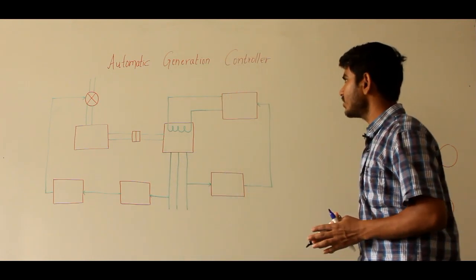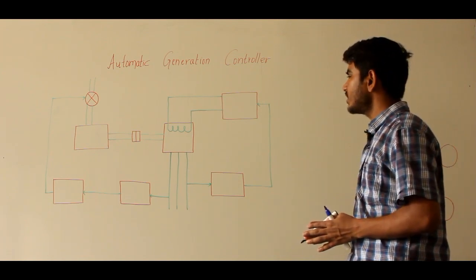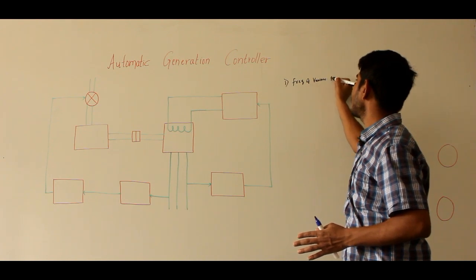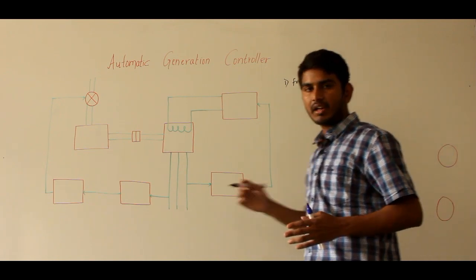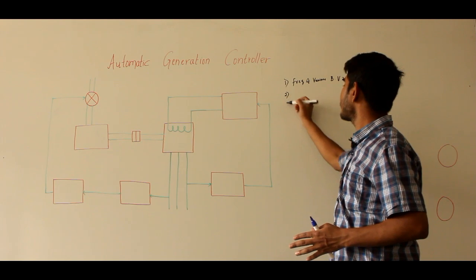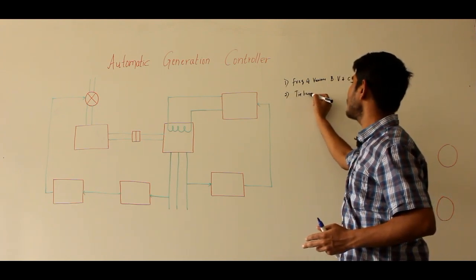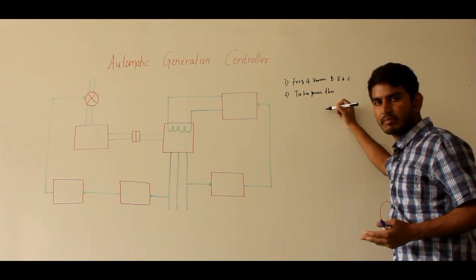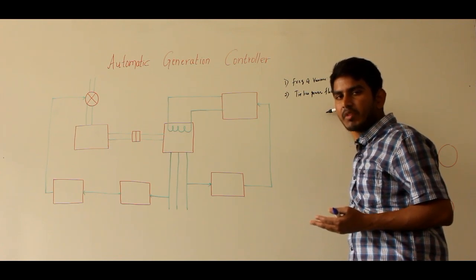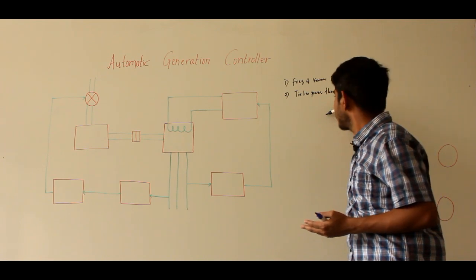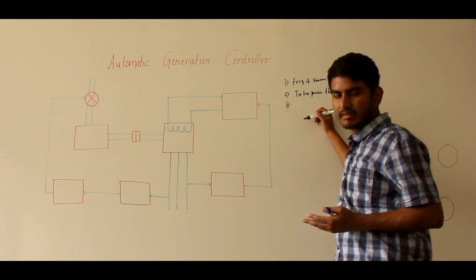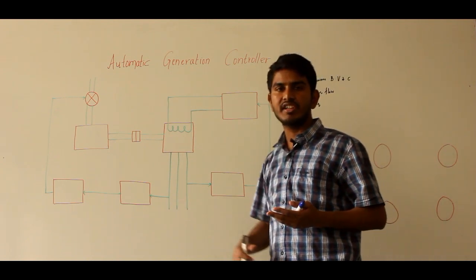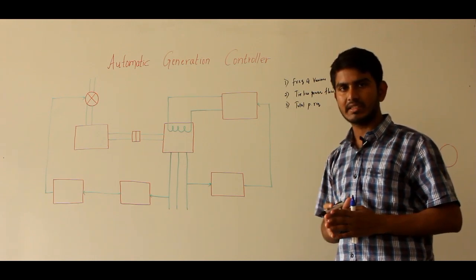The purpose of using AGC — the requirement of AGC — is to ensure three things. First, the frequency of various bus voltages and currents must be maintained at or near specified values. Second, the tie-line power flow among the interconnected areas must be maintained at specified levels. Third, the total power requirement on the whole system will be shared by the individual generators at an economically optimal fashion. This is the necessity of AGC.